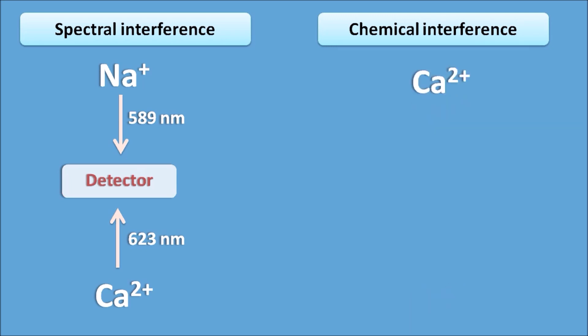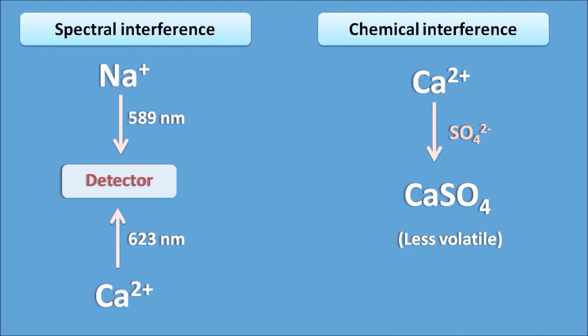Chemical interference is caused by anions. For example, if we are studying calcium and the solution contains sulfate ions, calcium forms calcium sulfate. Calcium sulfate is less volatile and cannot be converted into a gaseous ionic state, which decreases absorption or emission — this is chemical interference. Because this interference is caused by an anion, it is also called anionic interference. The right answer is that chemical interference is mainly due to formation of less volatile compounds like calcium sulfate.